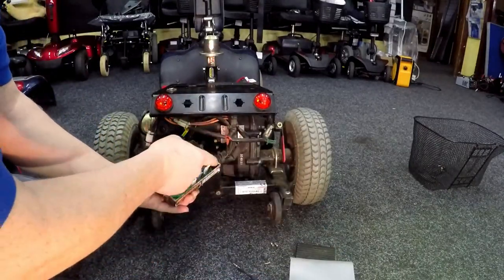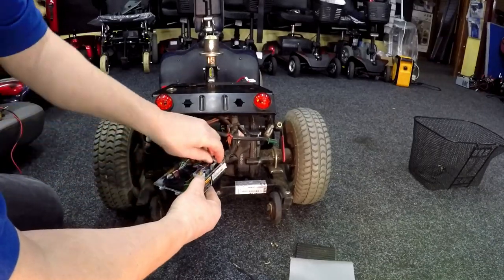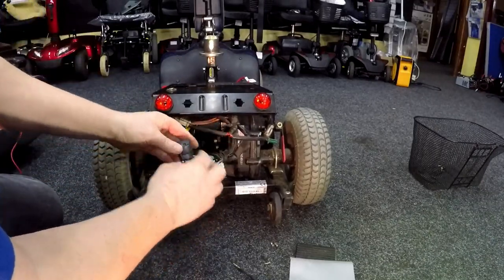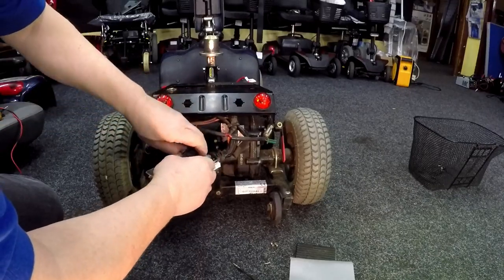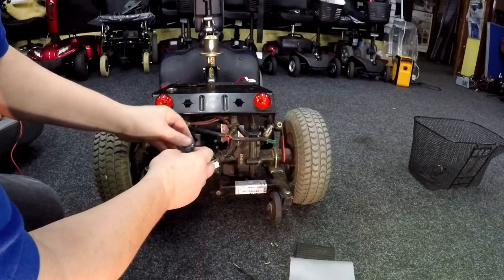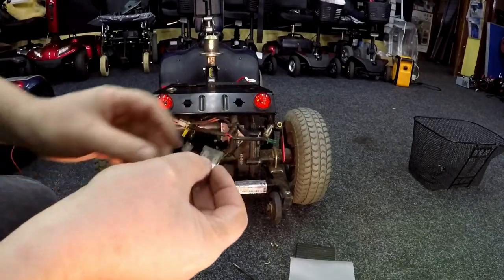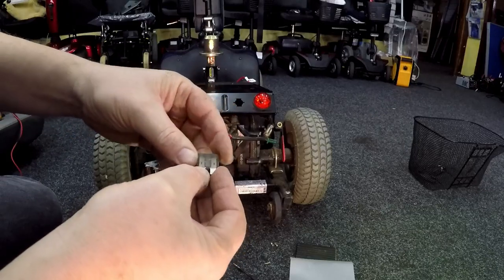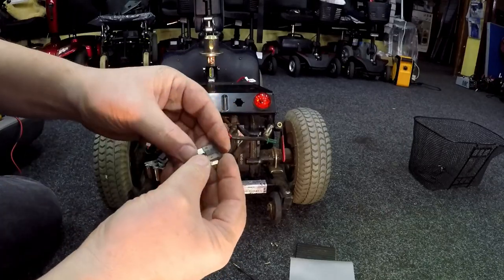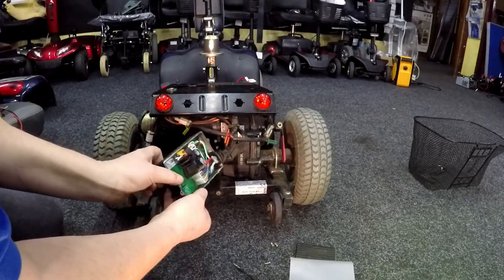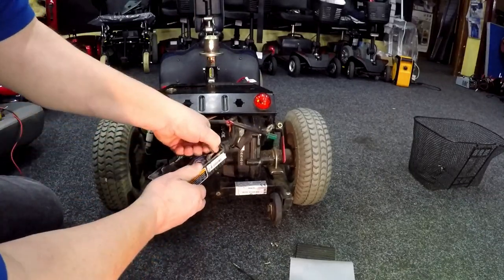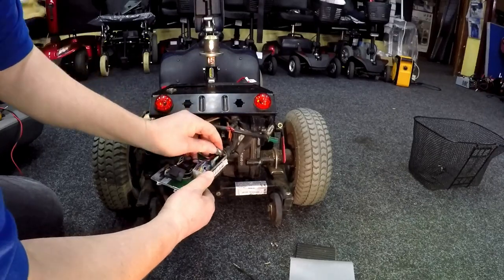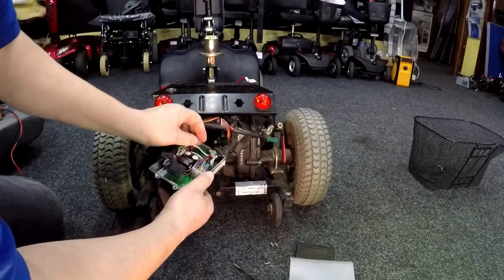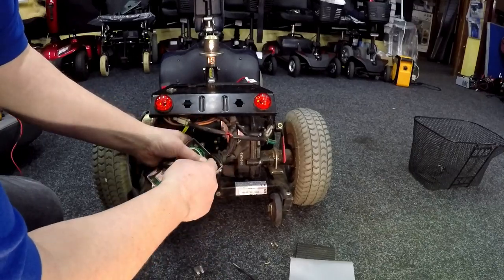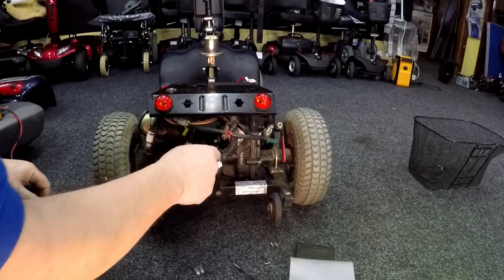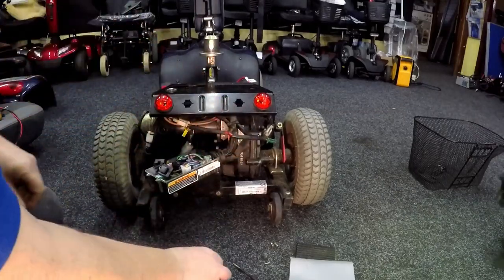So there's your control box, and straight away I see that particular connection's come off. Let's have a look at the fuse. Ah, there you go. Fuse is blown. You can see that there, it's blown in there. So that's going to be our problem. So I need to put that connection back on. That's your motor connector. And see there's a cable tie in there somebody's put in. So we need to get a fuse now and put a fuse in it.